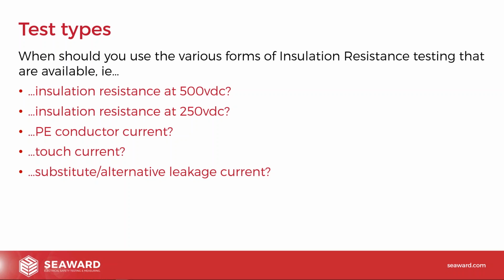So when should we carry out the various forms of insulation resistance testing that are available? What have we got available to us generally on most PAT testers? Well, we'll have a 500 volt DC insulation resistance test. We'll have a 250 volt insulation resistance test. We've usually got a protective earth conductor current test, or a touch current test, generally known as leakage tests, and the substitute or alternative leakage test. All of those will tell us something about the condition of the insulation within the equipment, and when should we use each one.